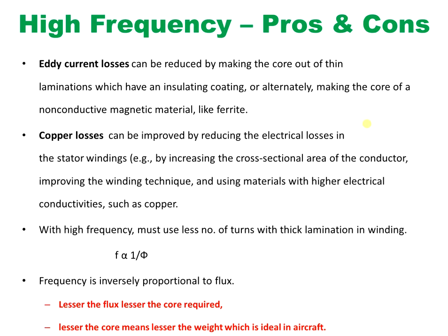If you face this question in an interview, remember one key thing: frequency is inversely proportional to flux. If frequency keeps increasing, flux becomes less. For lesser flux, a smaller core size is required. Smaller core size means less weight, which is ideal for aircraft. That's the reason 400 Hz is used — this is what you need to answer in those interviews.